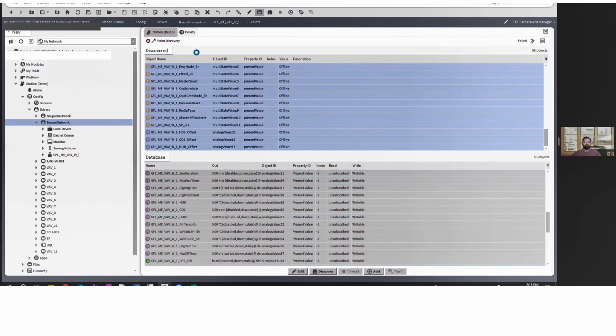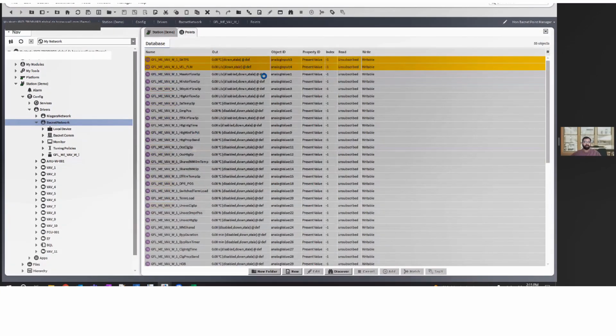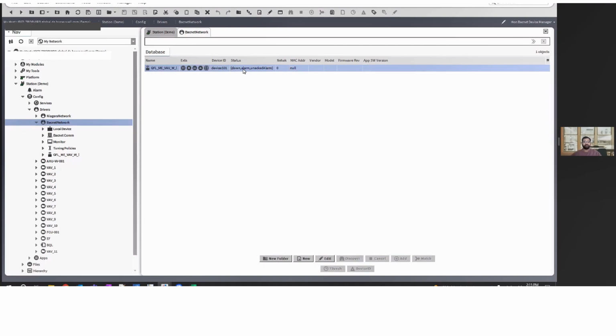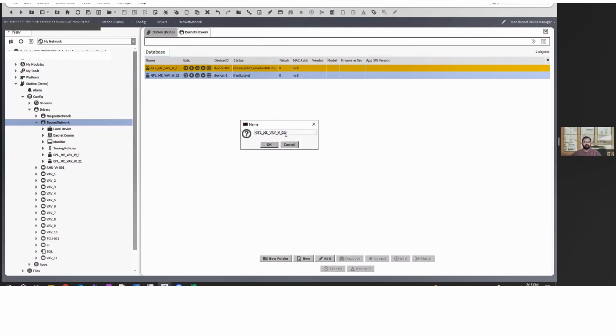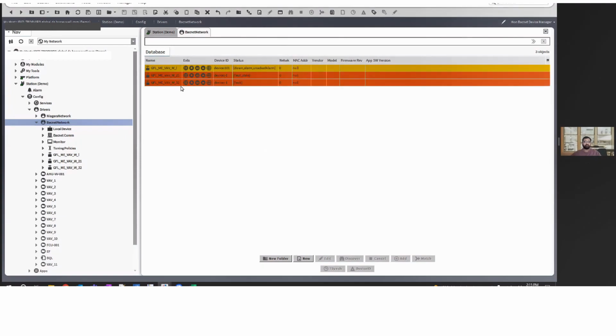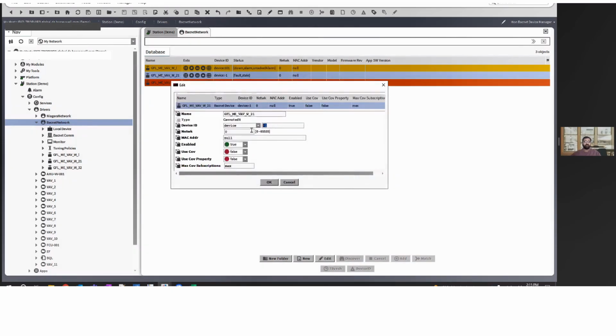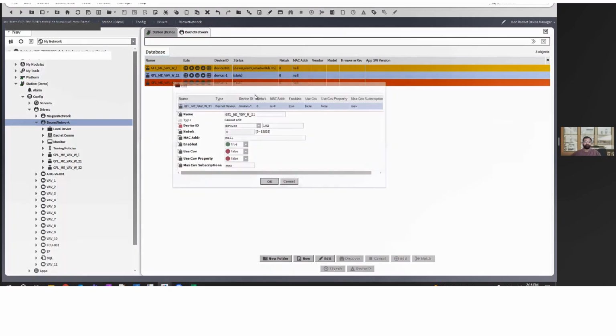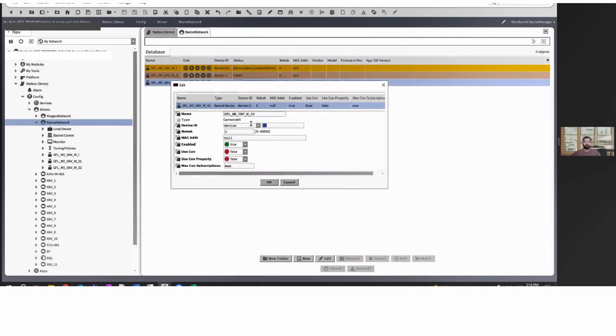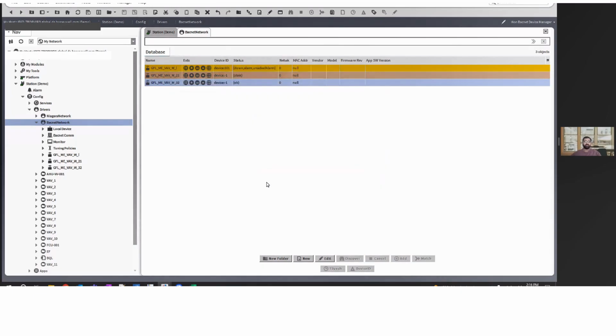Now once you have this VAV and you have assigned the facets and so on and placed it, the easiest way you can duplicate it, or the other way could be you can again import the EDE file into the Niagara database. If you duplicate, the only thing you need to take care is update the device ID and it will be all done. So your database for typical systems will be ready in like 30 minutes or so.